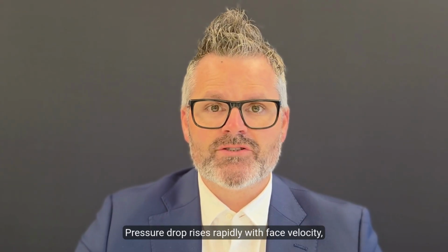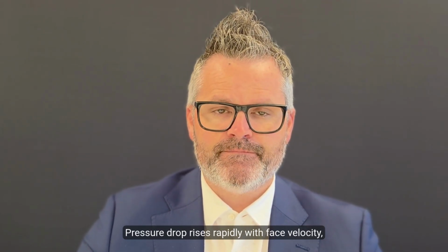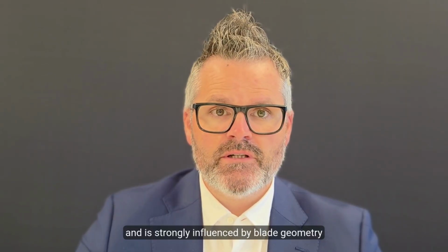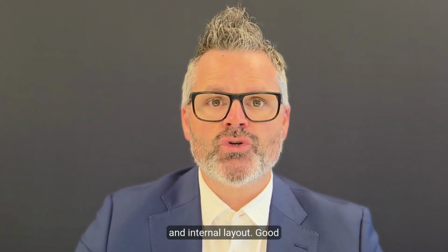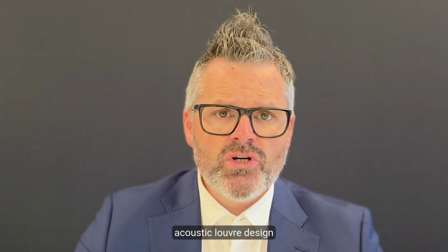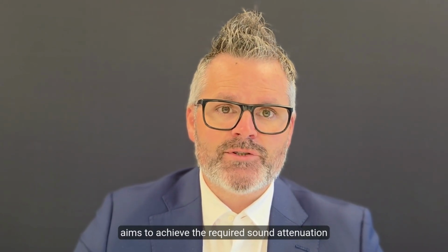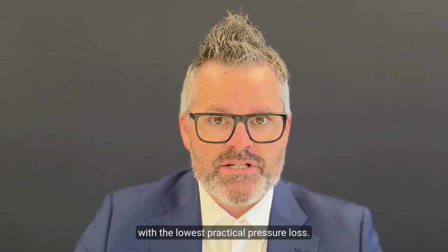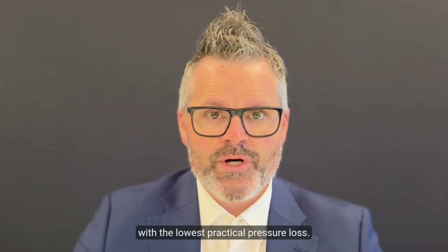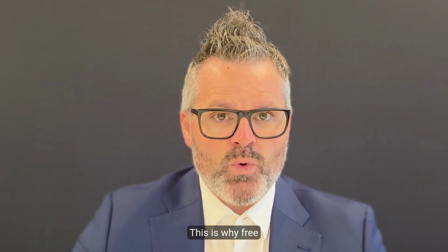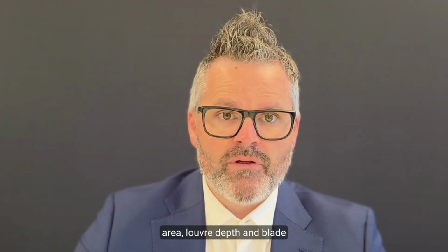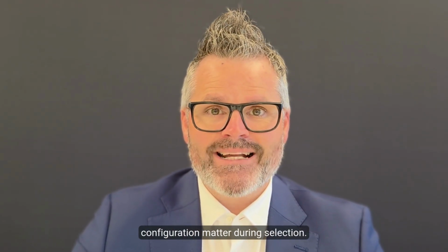Pressure drop rises rapidly with face velocity and is strongly influenced by blade geometry and internal layout. Good acoustic louver design aims to achieve the required sound attenuation with the lowest practical pressure loss. This is why free area, louver depth, and blade configuration matter during selection.